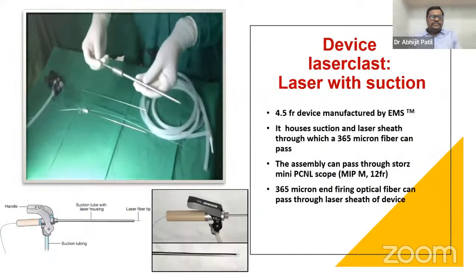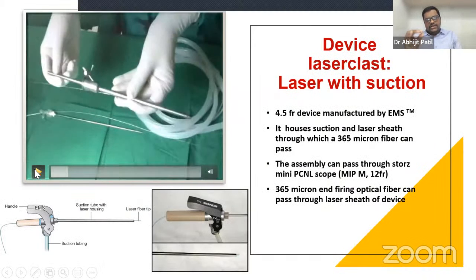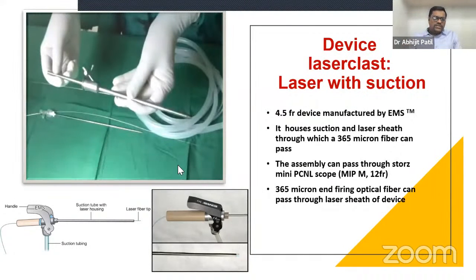Now the first device is a laser with suction. This was initially devised by EMS, where there was a suction tube with a laser housing in it, such that a 365 micron laser fiber could be passed through it. The laser tip could come out from here. You lase the stone and this housing would suck the fragments, which would get sucked out into the suction tubing. The amount of suction that the surgeon needs to apply can be controlled by the handle itself. And this is a 4.5 French device which can very well go through the 12 French mini nephroscope available from Karl Storz or Olympus.